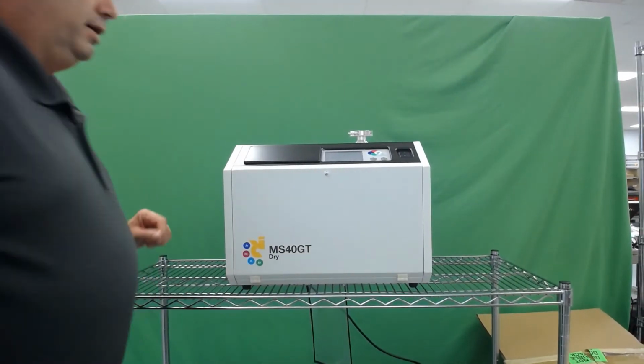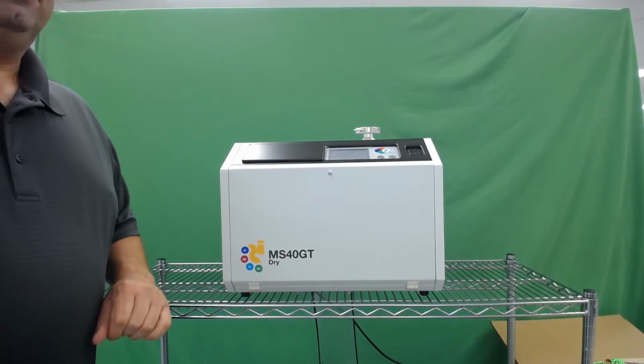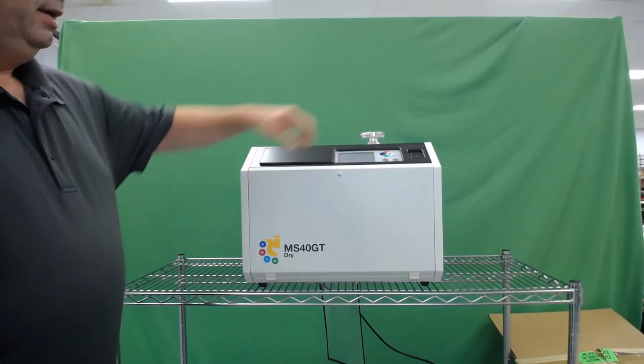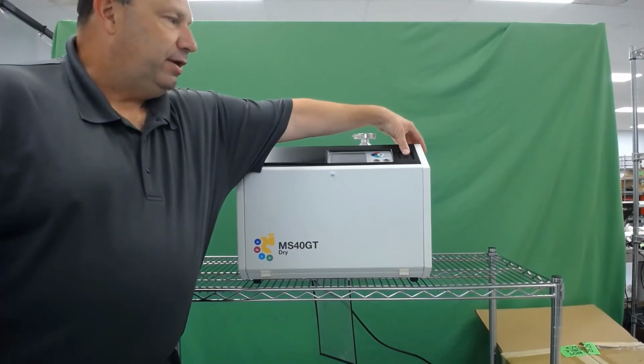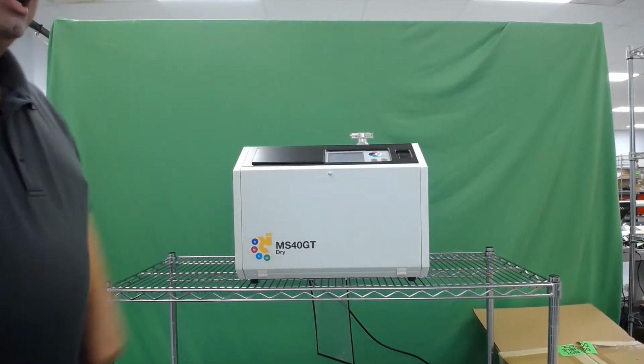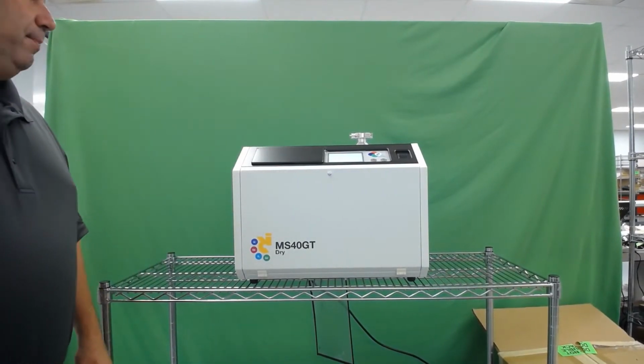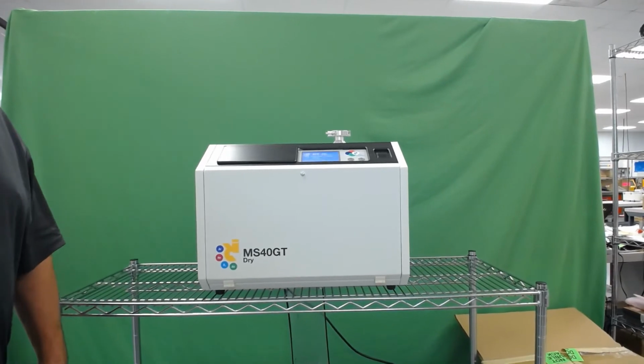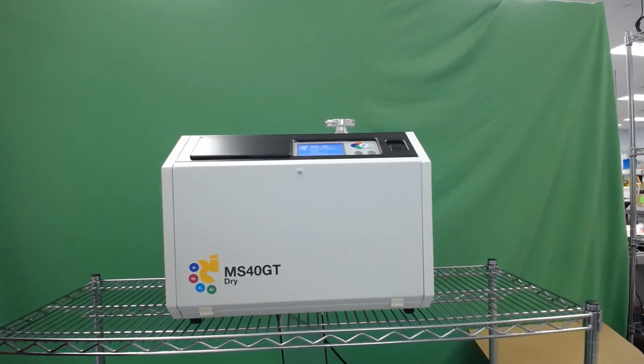After the machine is plugged in, there is no oil requirement. This is a dry, oil-free unit. Turn the main power switch on. The vacuum pumps and turbomolecular pump will start up, and the machine within 2 to 3 minutes will be ready for operation.